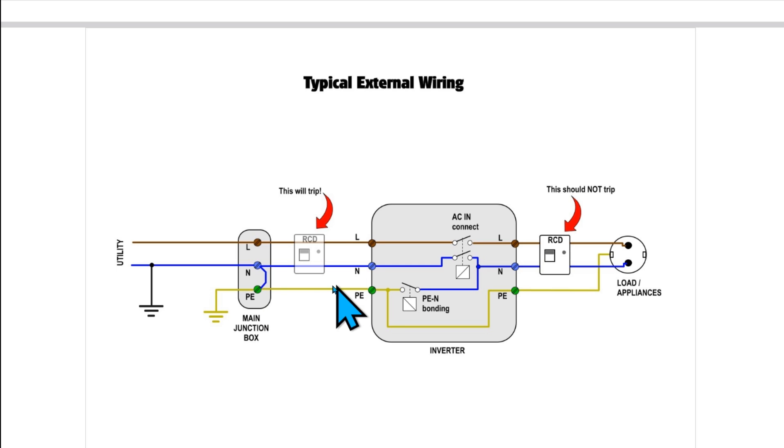This because the neutral and the PE are not at the same voltage even though they are connected here at the main junction box. In particular if you have long wires from here to here and particularly if there are some loads here, the voltage drop on the wires would be sufficient to make this RCD trip because there will be a certain current that would flow through the earth in this way.